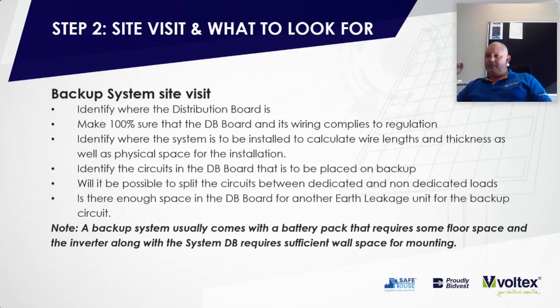On a backup system, only certain circuits will be allowed to be powered up. We call them comfort loads: lights, fridges, television sets, internet routers, etc. So you need to identify if it is going to be possible to split the circuits between dedicated and non-dedicated, or essential and non-essential loads. You need to look inside the distribution board as well to ensure that there's space for a second earth leakage unit. This earth leakage unit will be specifically for your backup system.